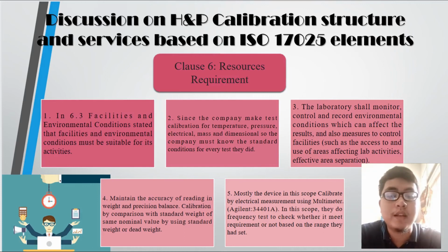of effective area separation. The company needs to maintain the accuracy of reading in weight and precision of the weighing scale. Calibration is by comparison with standard weight of the same nominal value by using standard weight or dead weight. Mostly, the devices in this scope are calibrated by electrical measurement using a multimeter. In this scope, they do frequency tests to check whether the device meets the requirement or not, based on the range they had set.